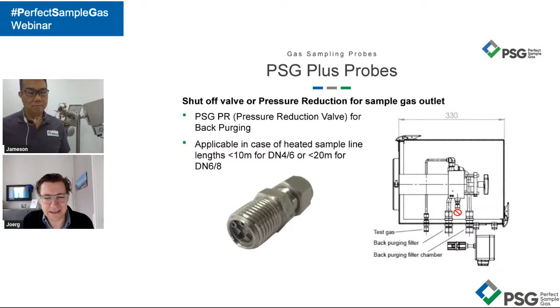James, only a few words left. I think this is also important when we talk about primary sampling. It's not only the filter chamber, but also what is happening in front, and maybe just some words about the sampling probes. Yeah, so when we choose the sample pipe, right? We know that it is against the process, corrosive or the temperature. Therefore, we have different materials for different processes. All right. So important things are, when it comes to corrosion, we can choose a very expensive material like Hastelloy or Kanthal, but at lower temperature, you can choose a PTFE.